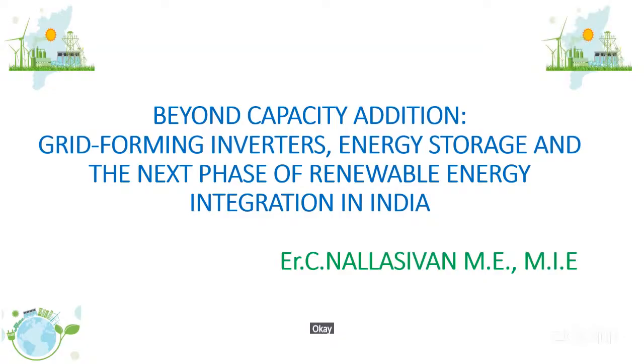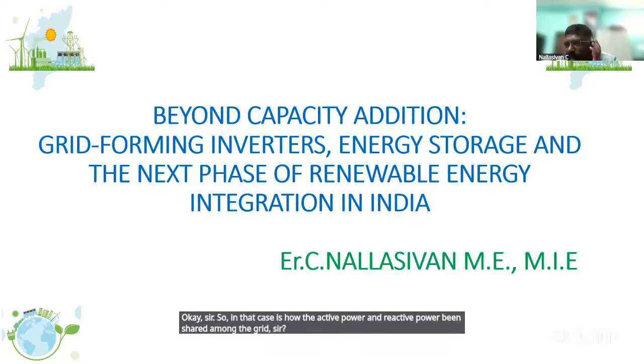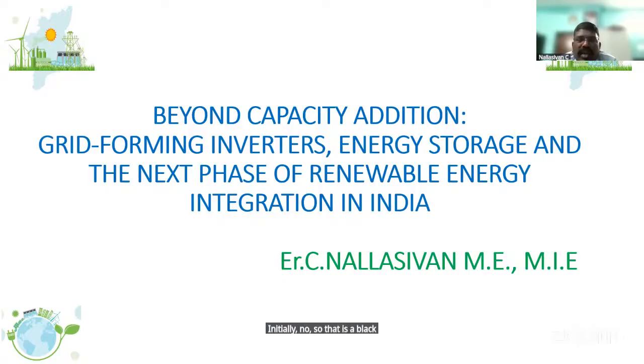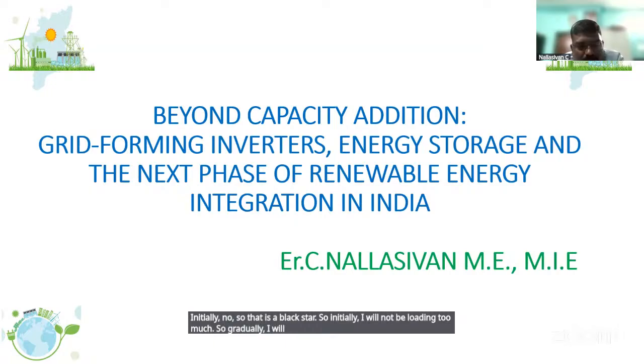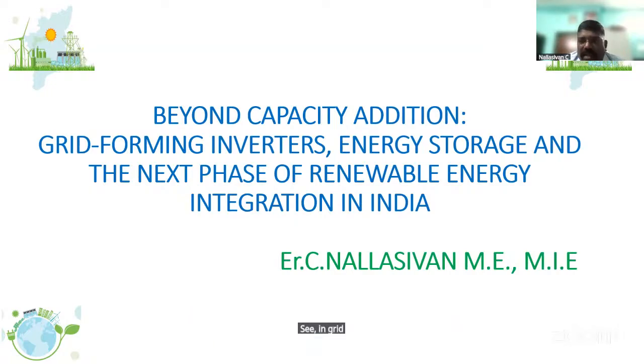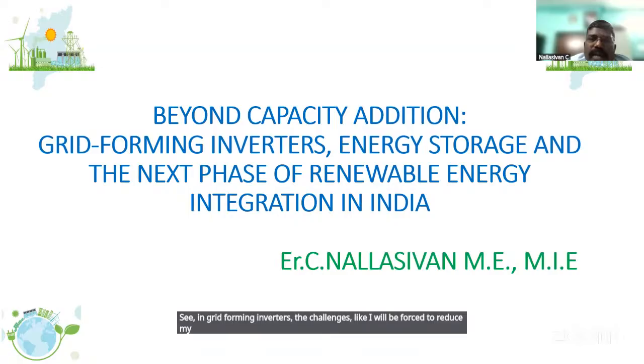Okay sir, so in that case, how are the active power and reactive power being shared among the grids? Initially no, since it's a black start, I will not load too much. Gradually I will be loading, and roughly it would be like one-third. In grid forming inverters, the challenge is that I will be forced to reduce my active power to support reactive power mechanisms.